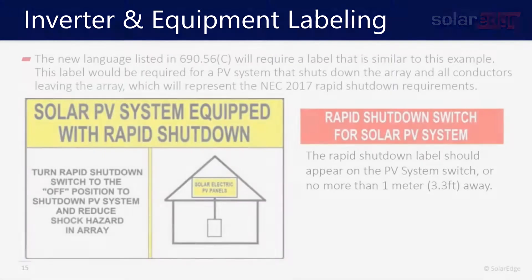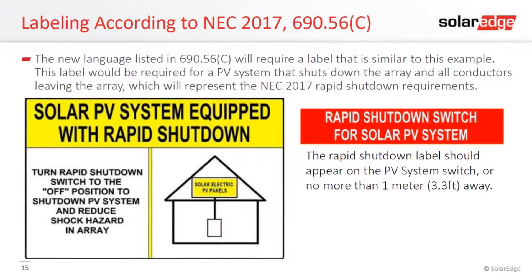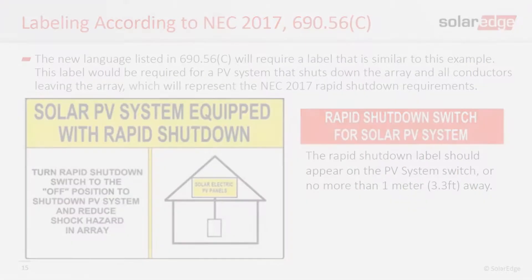Labeling for rapid shutdown changed a little bit in the 2017 code. The label reads: 'Solar PV system equipped with rapid shutdown — turn the rapid shutdown switch to the off position to shut down the PV system and reduce shock hazard.' This informs the first responder that there is less than 80 volts under the array.